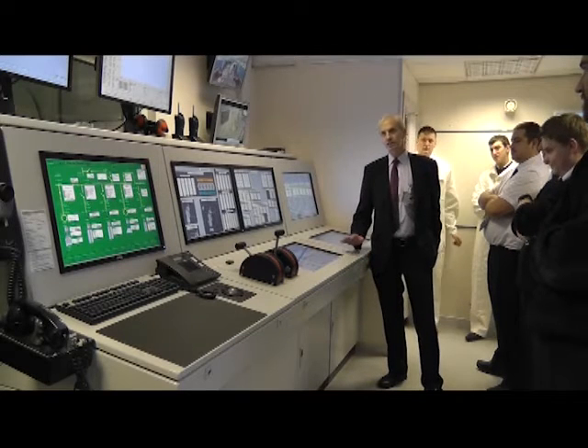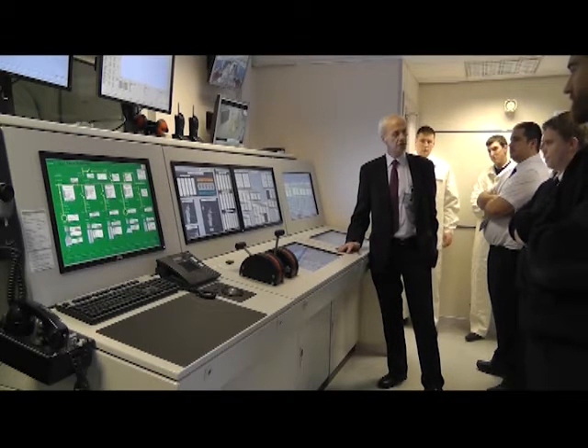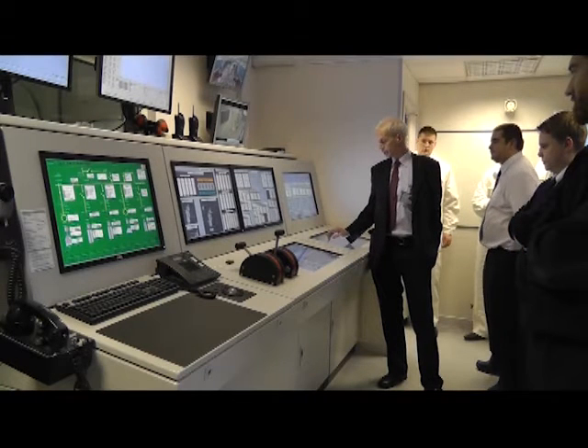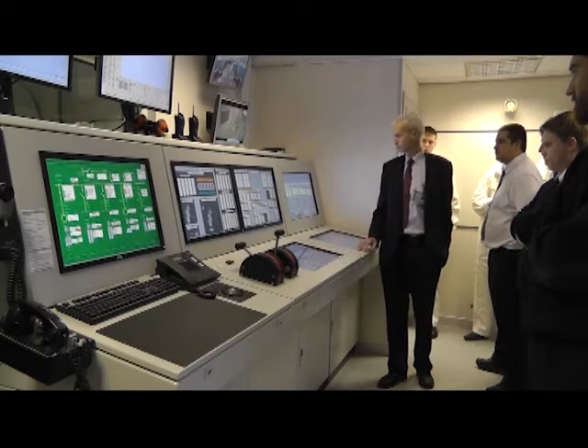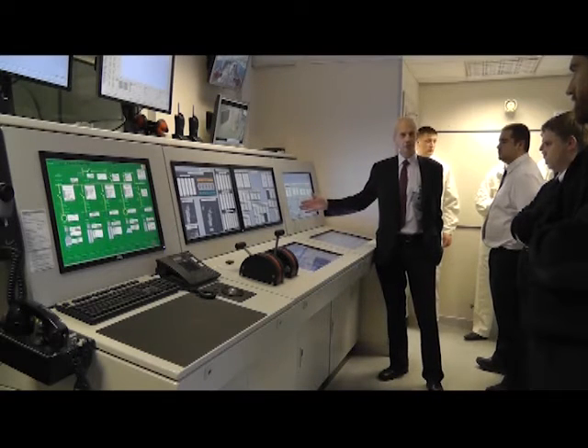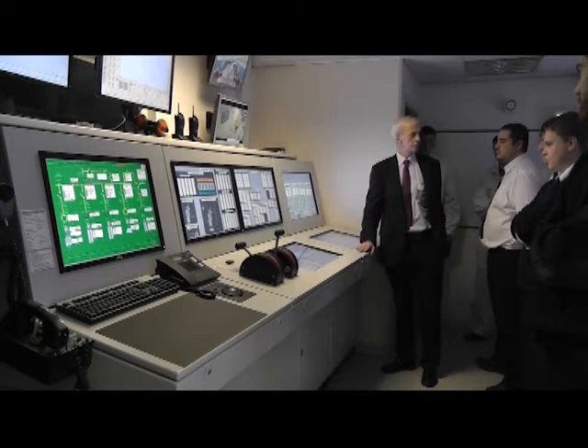The purpose of this short brief exercise is to demonstrate how important it is to set the systems up to ensure the automation does what it's supposed to do in the event of a power failure. What I'm doing now is increasing the load on the generators by starting extra pumps. That will cause the shaft generator to trip, and now the turbo generator's tripped and we've gone to blackout conditions.